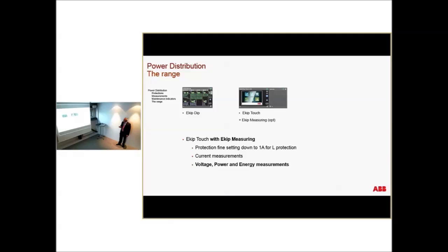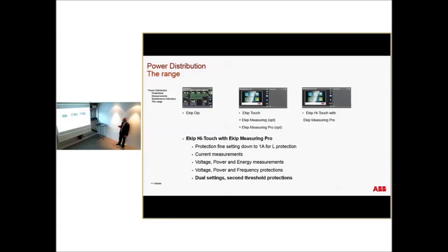You have the possibility to have the measurements. So you have a module that is put on the right side that gives the possibility to measure voltage, power, and energy. Again, you can have a second device as an alternative to measurement. It's called Measurement Pro, and in this case, you can also protect against over voltage, directional protection, reverse power, active power, all things like that. So for everything related to the voltage, you can have a protection. Again, the Hi-Touch has the dual setting and the second thresholds protection.